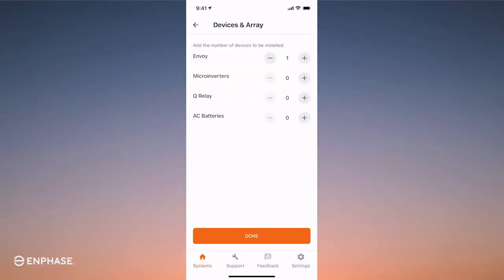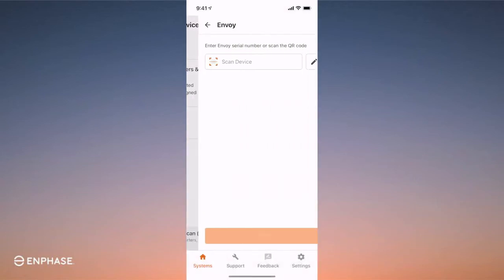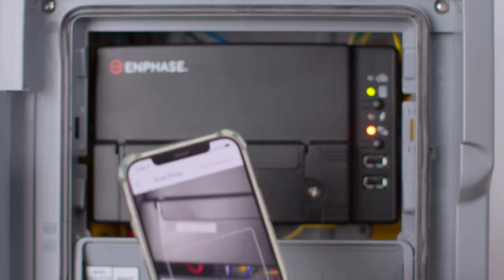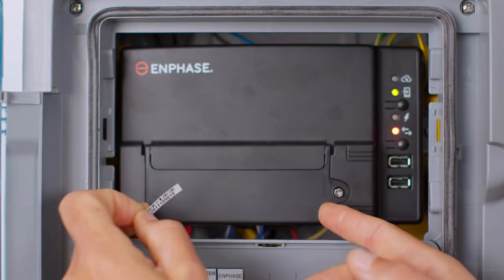Notice that Stage 1 is completed and green. Now go on to Stage 2. In Stage 2, you are programming the Envoy with microinverter serial numbers. I will show you a simple method for quick scanning of these microinverters. Enter the correct number of devices and select Powerline scan for devices. Now you'll need to add the Envoy serial number — you can manually type it in or scan it. Here I'm scanning the serial number. Pro tip: make the serial number easier to access by peeling off the serial number sticker and fixing it to the front of the Envoy.